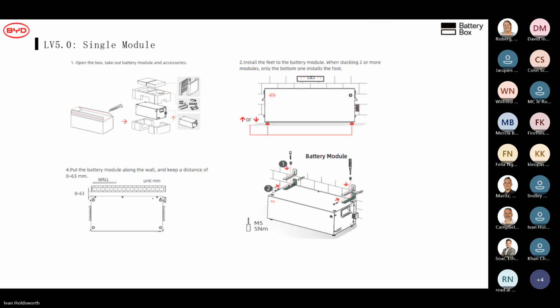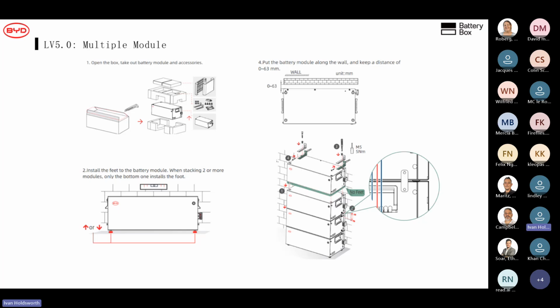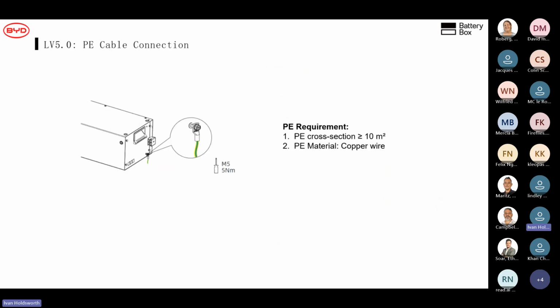And then you can see the box and how to take it out. And then you've got various options. You can either install the feet and have that as a bottom module. Please don't install the feet on any modules that are installed above that module. And here we can see it's installed on the wall, and you can see the installation of the earthlinks. It's always recommended to connect your earth for the purpose of good comms.